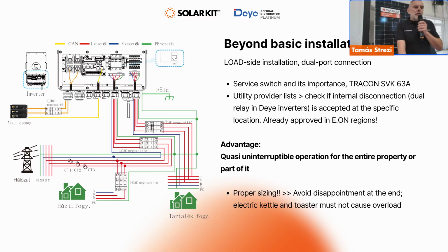But in this connection, you can also support house loads during a blackout or overvoltage conditions where your grid tie inverter would otherwise just disconnect and you would lose the whole generation. Okay, as I said, the proper connection of the neutral and RCD devices are critically important, because basically in this case you are creating your own electrical network, which is under voltage pretty much at all times.